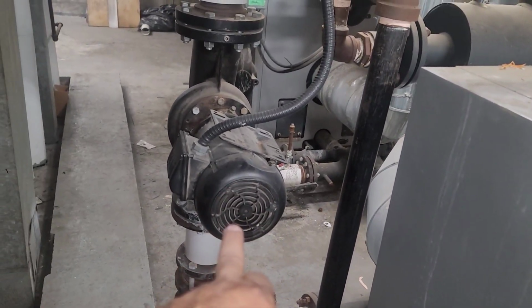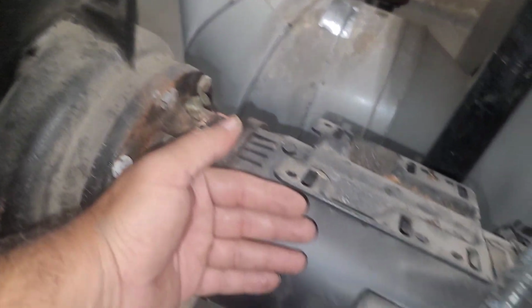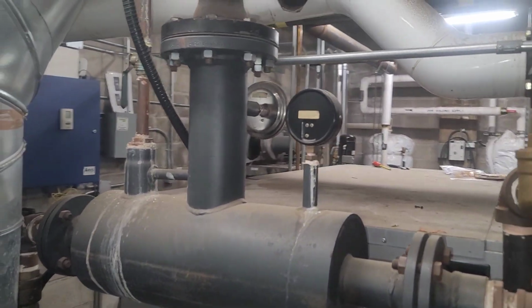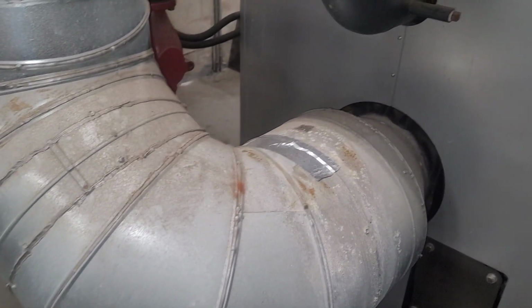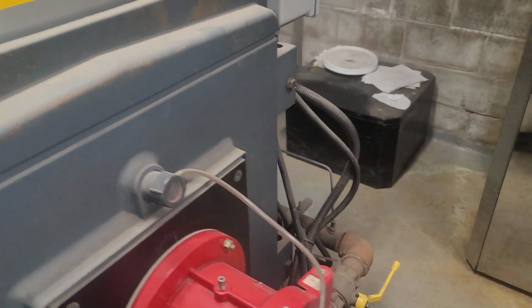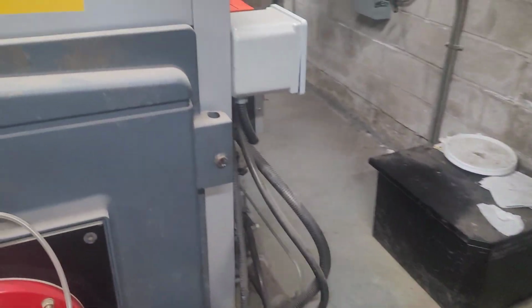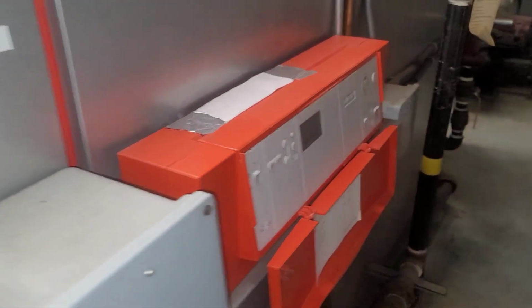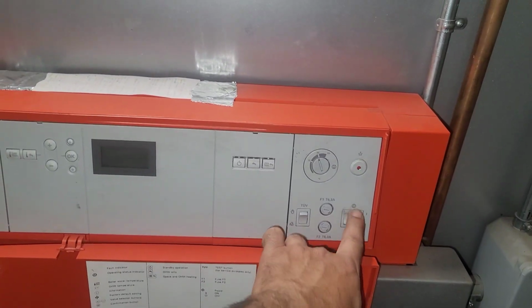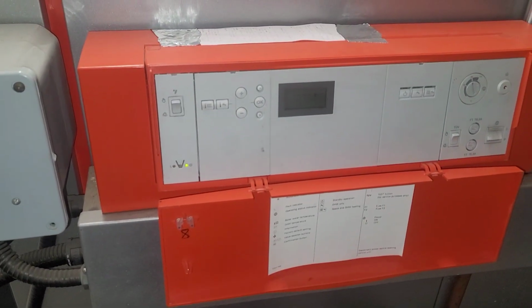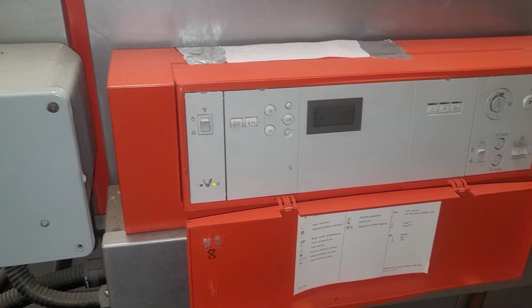So this is the boiler circulation pump, so we have to turn it on, and right now it's running. I have turned it on, and this boiler doesn't have a flow switch. This is a low water cutoff, and that's pretty much it, I think. We are not turning on the main circulation pump for the building, only the boiler circulation, because we're gonna test fire it just to verify if it is working with the new burner, igniter and flame sensor.